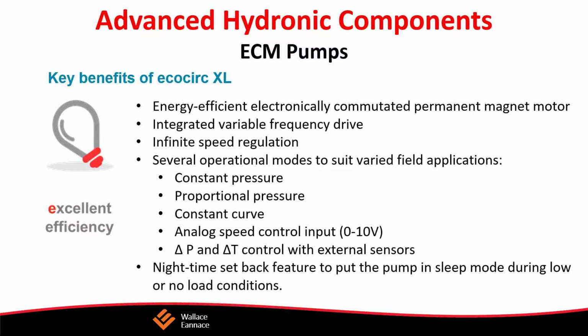There are 4 control modes: proportional pressure, constant pressure, constant speed, and an automatic night mode. These units come built in with Modbus and BACnet communication. They can communicate with a laptop through an RS-485 connection. And the EcoCirc XL is a high performance pump that takes efficiency to advanced levels through the use of ECM permanent magnet technology. It has state-of-the-art hydraulics, advanced motor design, and truly intelligent controls. There are all kinds of connections on there you can use. You can pump these units in parallel.